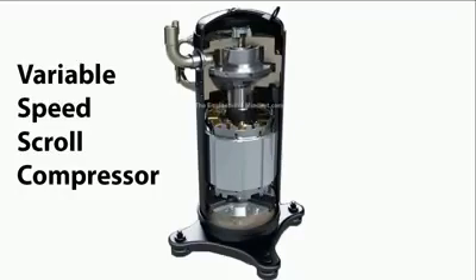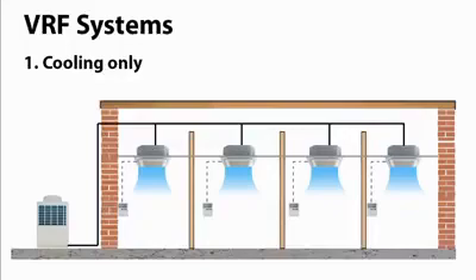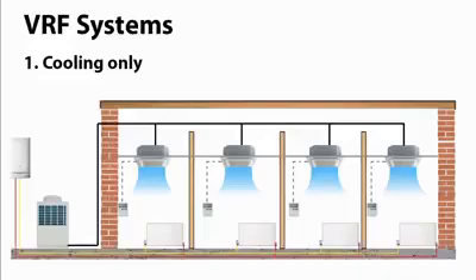multi-split AC unit. Now the cooling only VRF units, like I said, they only provide cooling, so they are typically used in warmer climates where there isn't the requirement for heating, or they could be placed within a building in a cooler climate which only has a need to reject heat, such as a computer and server rooms. Now these could also be installed within buildings in colder climates, but you're most likely going to need an additional heat source, such as perimeter radiators or just a combi boiler system.